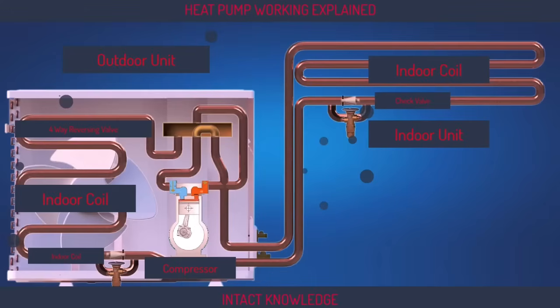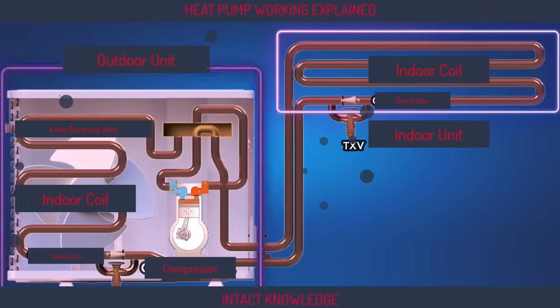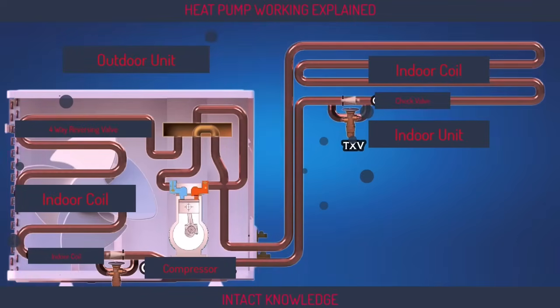As we mentioned earlier, a heat pump is essentially the same as the regular AC unit we use. It consists of an indoor unit, which is inside the house, and an outdoor unit, which is outside the house. Inside these units, there are components like the indoor coil, outdoor coil, and compressor, which are things we are already familiar with. But in addition to these, a heat pump has two extra check valves, or non-return valves, and two expansion valves. One expansion valve and one check valve are located in the indoor unit, while the other set is in the outdoor unit. Additionally, the system includes a four-way reversing valve with two inlets and two outlets. This valve contains a solenoid that switches the system between heating and cooling modes based on the thermostat settings.